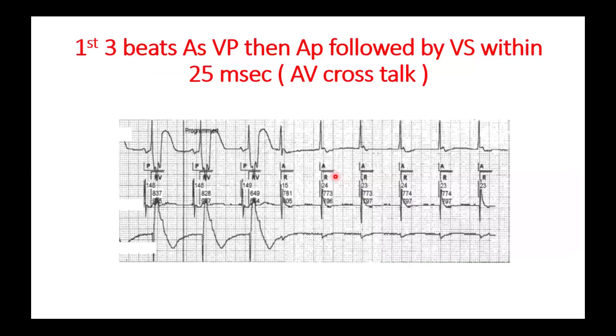Here is the explanation. So this crosstalk is the ventricular channel sensing the atrial pacing spike, so it reacts as V sensing. Here you can notice that there is no depolarization on the ventricular EGM. The ventricular EGM is just sensing the atrial pacing, and there is asystole of the ventricle. Here just atrial pacing, atrial pacing, atrial pacing, while during atrial sensing there is no such problem.